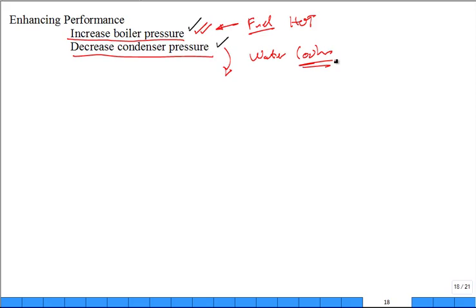as low as your lake water temperature, or closer to the lake water temperature, or closer to the outdoor ambient temperature. And if you work for a power plant that makes electricity, you'll actually see the fluctuation, because the coal burns just as hot in the middle of December as in the middle of August. Okay, they're going to continue to have metallurgical considerations on your equipment for the high temperature in the furnace. But the lake water fluctuates. December, it's actually cooler lake water in Texas than in August. So basically it runs a little better in the winter because of the cooler lake water temperature.